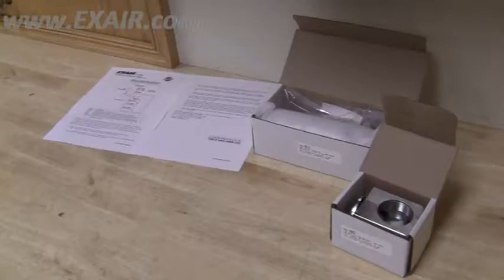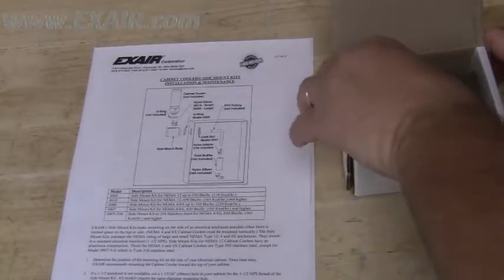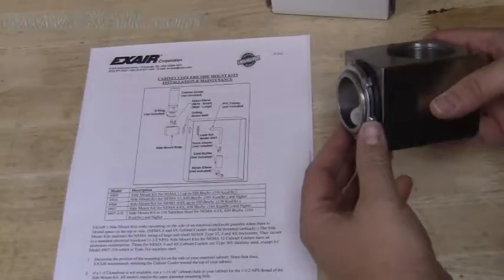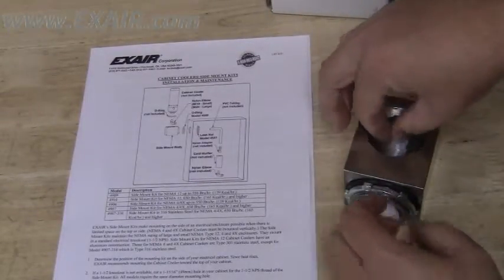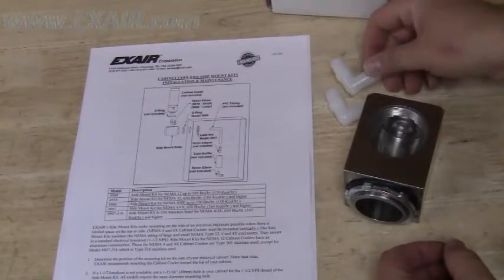Side mount kits come complete with all the fittings necessary to complete installation of an EXAIR cabinet cooler system: the side mount body itself, locking ring and O-ring for sealing to the enclosure, and nylon elbow or elbows to connect the cold air distribution hose and muffler when specified.